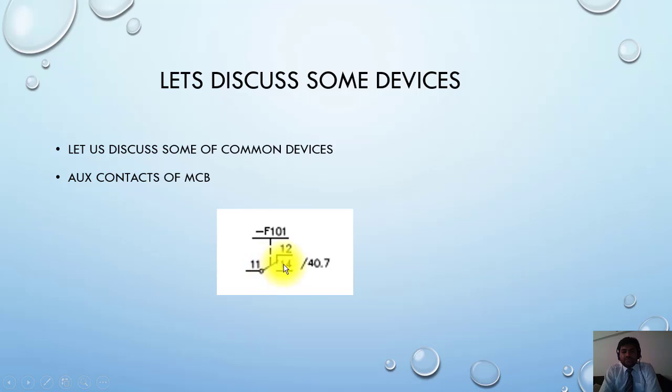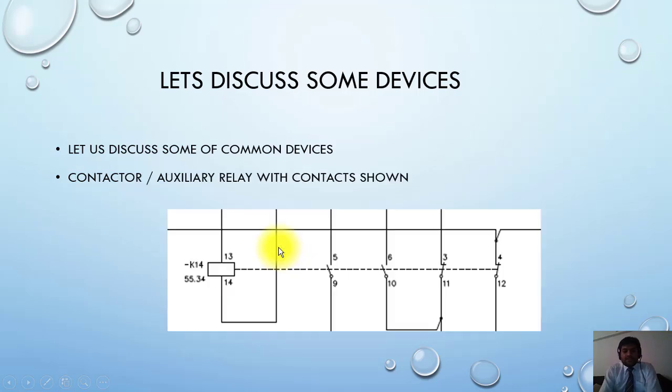Let us see another item which is very common - it is auxiliary relay or a contactor. So this 13 and 14 is the power supply of this contactor or its coil. When this coil is picked up and supply is provided or connected to this relay K14, then this contact will change from open to close.